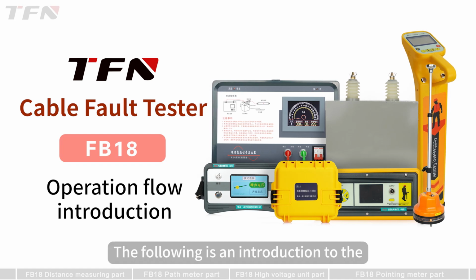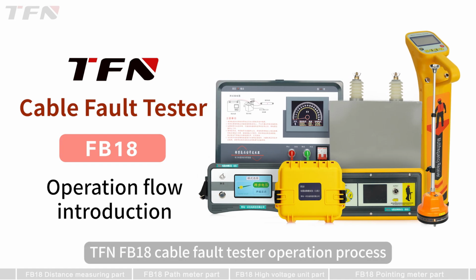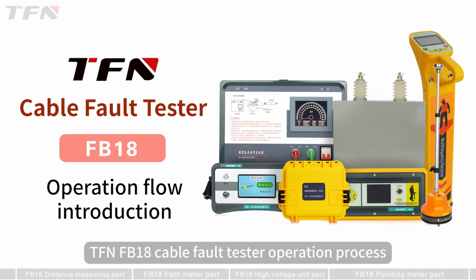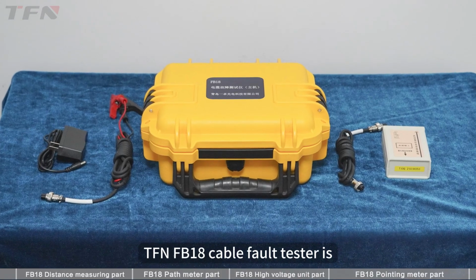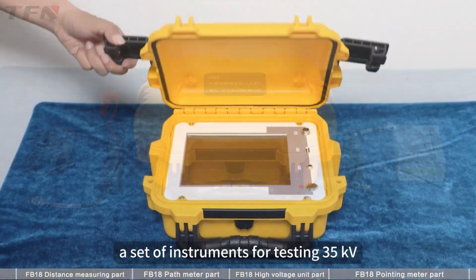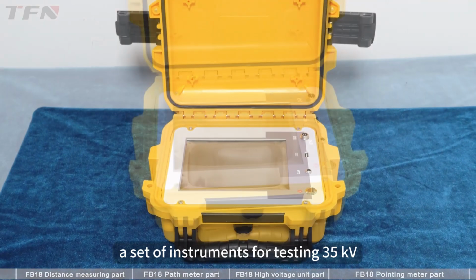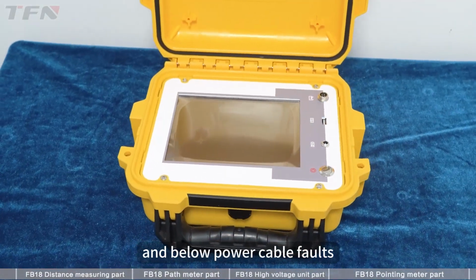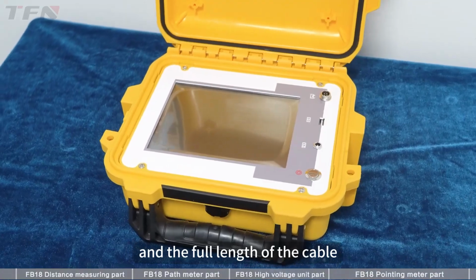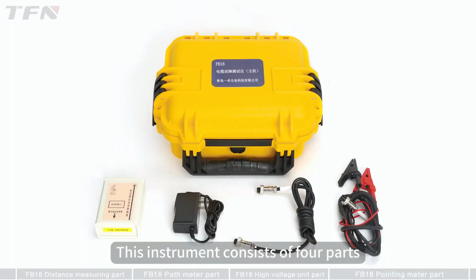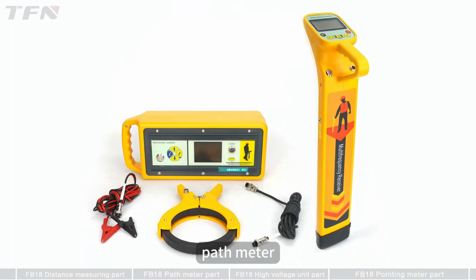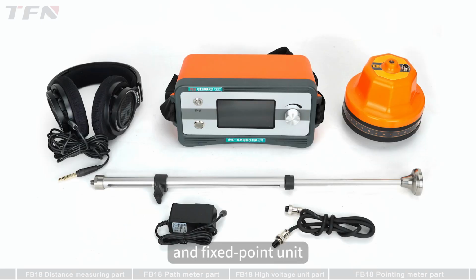The following is an introduction to the TFN FB18 cable fault tester operation process. The TFN FB18 cable fault tester is a set of instruments for testing 35 kV and below power cable faults and the full length of the cable. This instrument consists of 4 parts: distance meter, path meter, high voltage unit, and a fixed point unit.